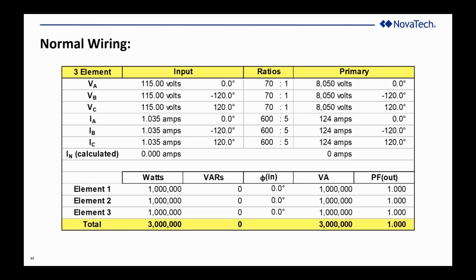Here's a normal connection. I flipped two of them. I flipped them by 120 degrees because I'm flipping phase B and phase C. So now the B phase is where the C phase should be, minus 120. And the C phase is at minus 240. What did I do there? Minus 240 is plus 120, which is where the B phase should be. All I did is I forgot to add 360 to make it from 0 to minus 120. So it's correct. The B phase angle is where the C phase should be, and the C phase angle is where the B phase should be. Those are the two wires that are flipped.